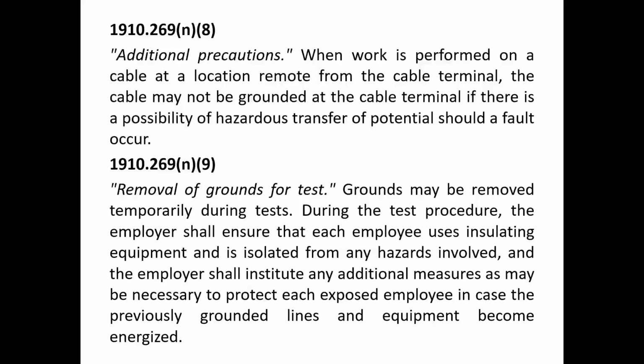Grounds may be removed temporarily during tests. During the test procedure, the employer shall ensure that each employee uses insulating equipment. So you've got to use insulated rubber gloves and be isolated from any hazards involved, and the employer shall institute any additional measures as may be necessary. And there are quite a few that you could fall into. Don't mean that intentionally.